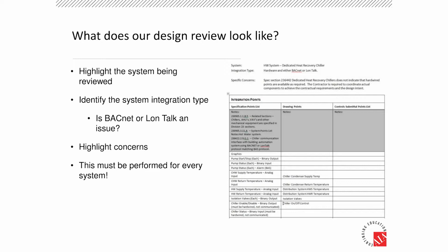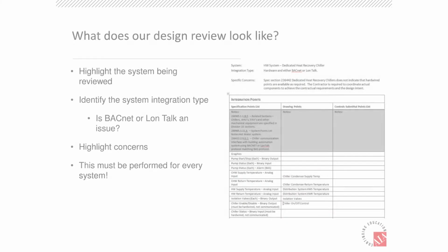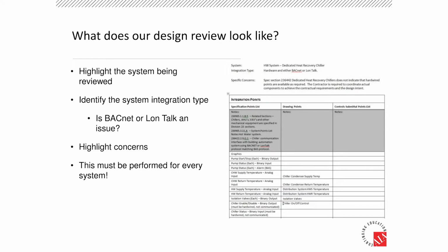But then when we read further in the specs, the spec and the information on that dedicated heat recovery chiller didn't require any kind of hardware points to be output. It didn't very explicitly say what was going to be communicated out. So that was a concern I had when we started doing the design review. This was a particularly nice design where it had an extensive points list that lived in the back end of the submittal, so I was able to pull all that data. And then when I start doing the drawing review, I start back checking to see what points were addressed in the drawing versus what's been left out. So the fact that this piece of equipment had pump start stop and pump status in the points list, but had nothing on the drawings requiring that as any kind of communication point, hardwired, integrated, whatever, it wasn't addressed in the drawings. So we start highlighting those issues and putting it back to the design team saying, let's tighten this up. Okay?